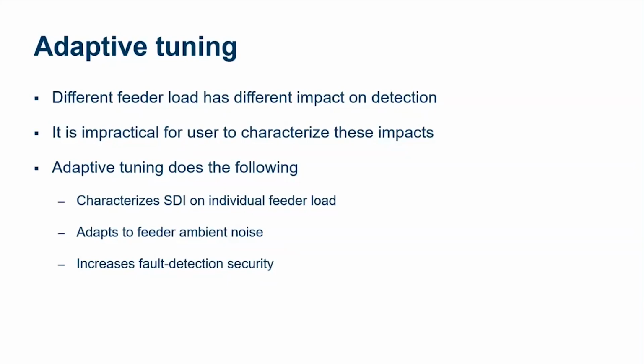So it's important that this element be able to tune to and adapt to the particular circuit where it is applied. And that is part of what AST does: it actually tunes to the circuit, and it's going to characterize what the typical sum of difference currents, that interharmonic energy, is going to be for that particular feeder. And then as conditions change, it is going to be able to adapt to those changing conditions in order to adjust and make sure that our element is still secure. We have changes to the loading.